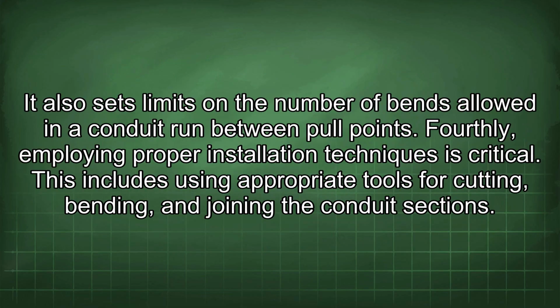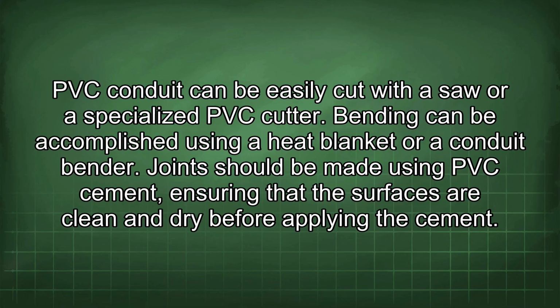It also sets limits on the number of bends allowed in a conduit run between pull points. Fourthly, employing proper installation techniques is critical. This includes using appropriate tools for cutting, bending, and joining the conduit sections. PVC conduit can be easily cut with a saw or a specialized PVC cutter. Bending can be accomplished using a heat blanket or a conduit bender. Joints should be made using PVC cement, ensuring that the surfaces are clean and dry before applying the cement.